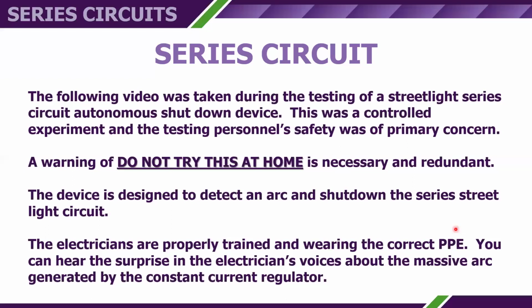Now, the next video you're going to see was taken during testing of a streetlight series circuit autonomous shutdown device. This was a controlled experiment, and the testing personnel's safety was a primary concern. A warning of "do not try this at home" is necessary, and it's also redundant. When you see it, you'll know why. The device was designed to detect an arc and shut down the series streetlight circuit. And believe it or not, series streetlight circuits are where our Airfield lighting technology came from.